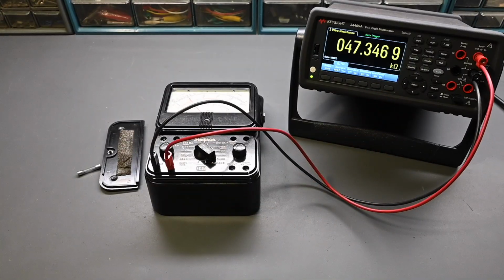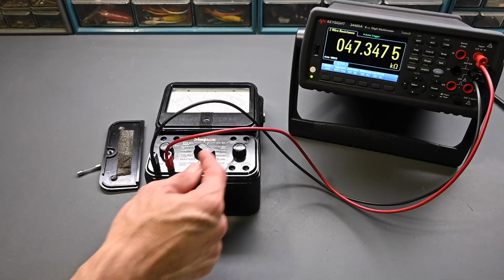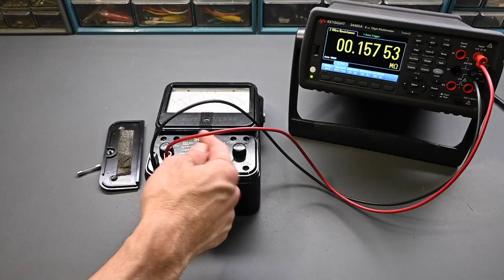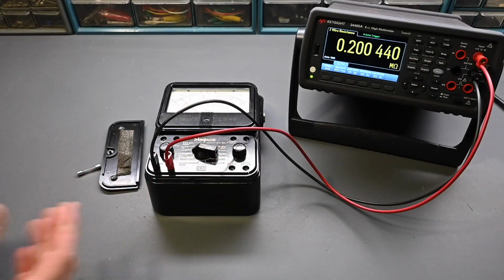So on a 2.5 volts full scale, that should be 50,000 ohms. 2.5 times 20,000 is 50,000. We're shy of that, so there's a bit of a problem there, but we are seeing an increase in resistance. So the multiplier resistors are in circuit, and we know that this switch is having an effect through the switching and the contacts. It's not a complete open circuit, but it's definitely not the right readings.